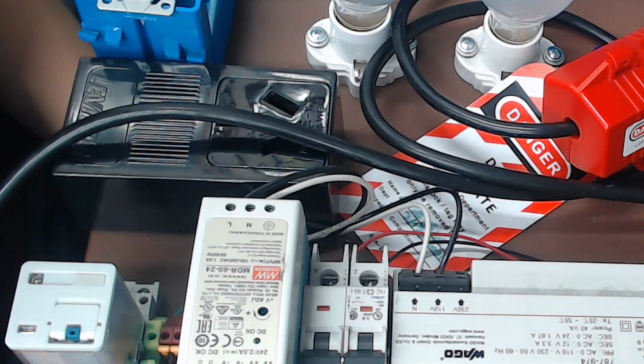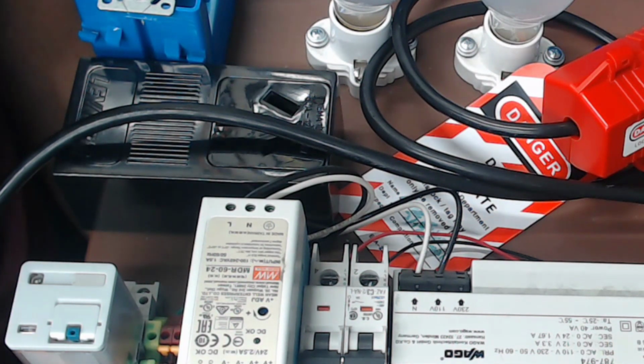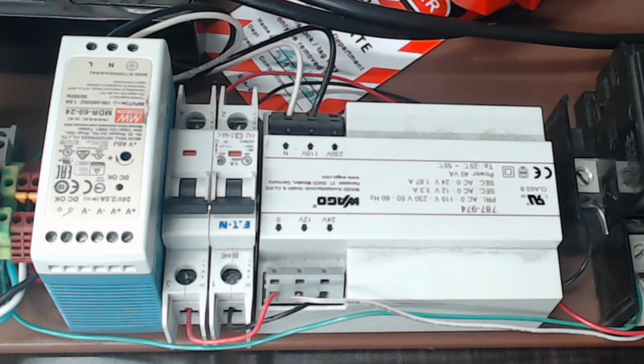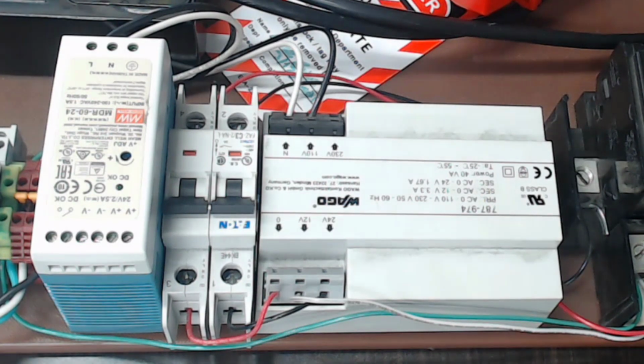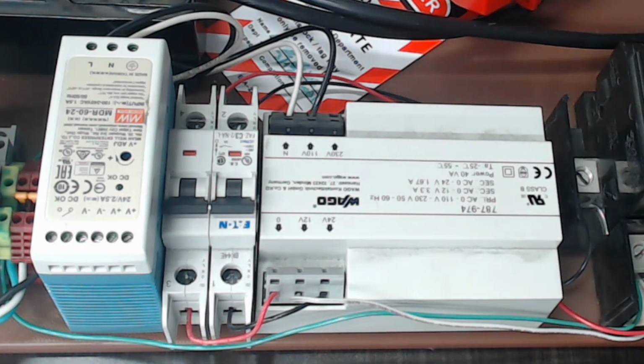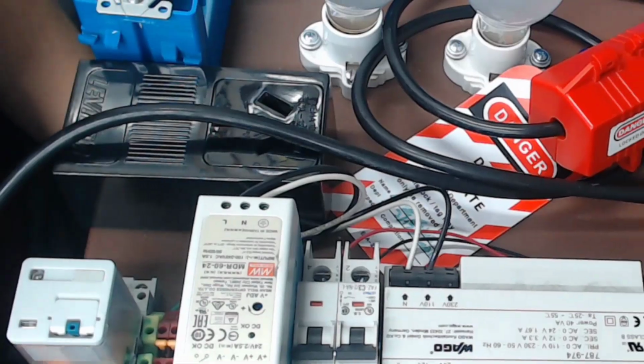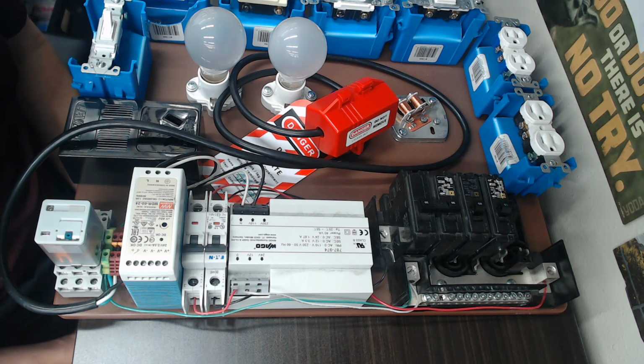A word of caution here: if you see any of your black or white wires that are coming in from the cable or that are going to the 24 volt DC power supply or the 24 volt transformer showing exposed copper, please do not plug it in and contact your instructor so that they can fix it so that it is not dangerous. Again, please contact your instructor if you have any exposed wires here, because that is 110 volts AC and it could shock you. That is our breadboard trainer. You may use this, or you may use any of the other trainers that we have for basic electrical. Thank you.